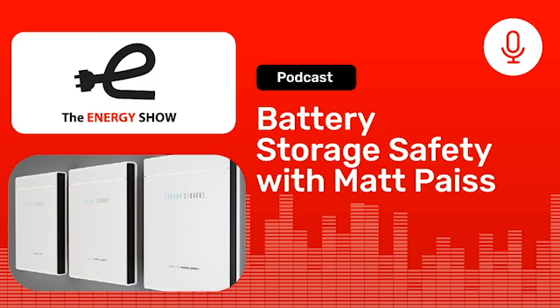The communications really involve a really important piece of equipment called a battery management system, or BMS. The job of the BMS is to monitor the voltage, current, and temperatures of those cells in a module or a whole unit or rack. The BMS is really a critical safety component, making sure the battery isn't charged too fast or at too high a voltage, or discharged too low or too fast. The BMS is really the key brains of a battery.